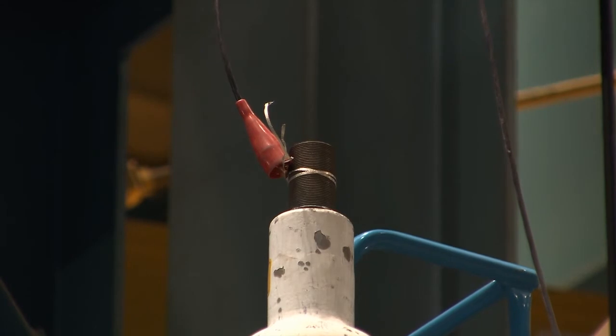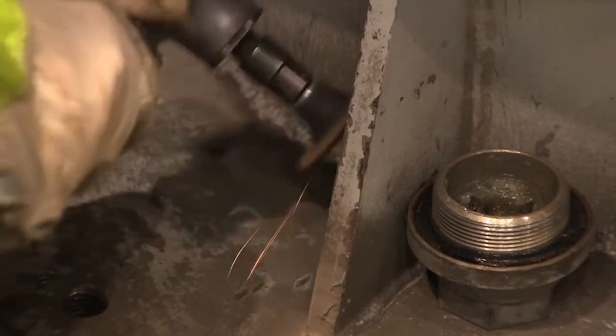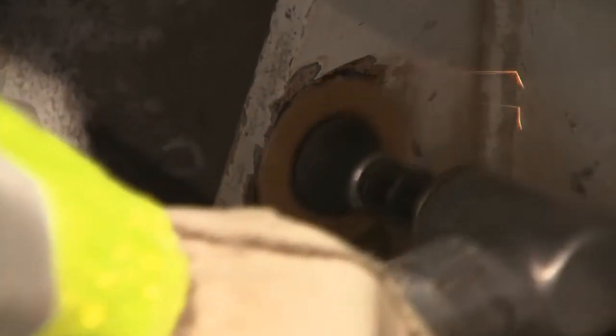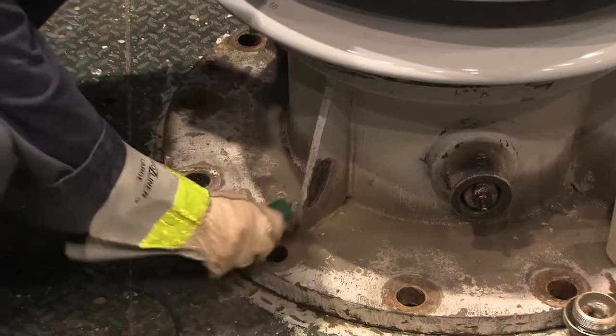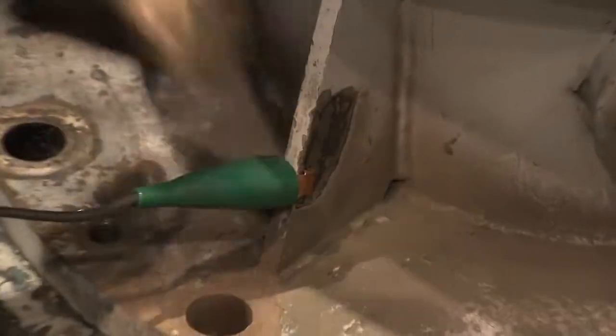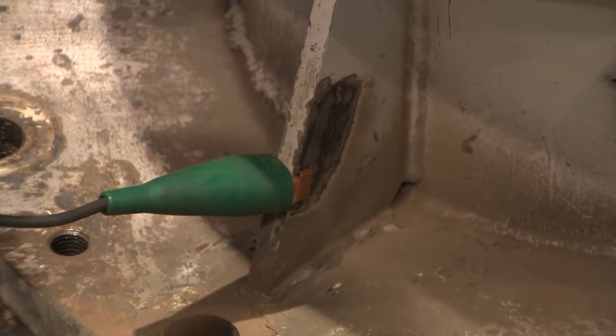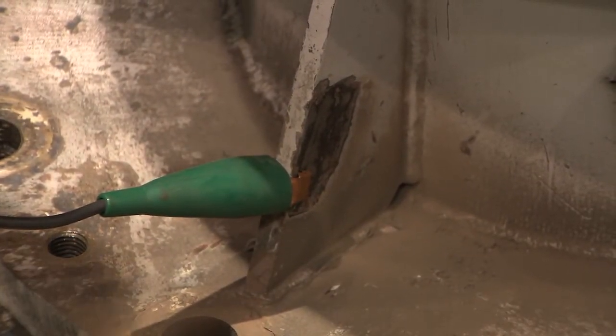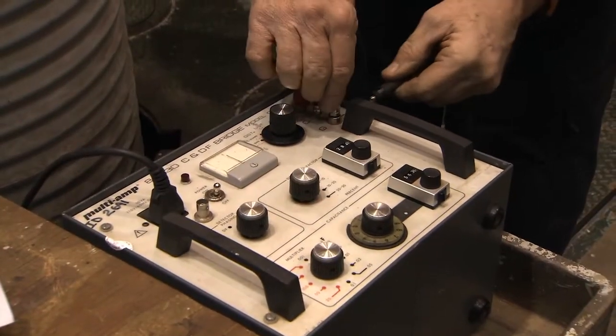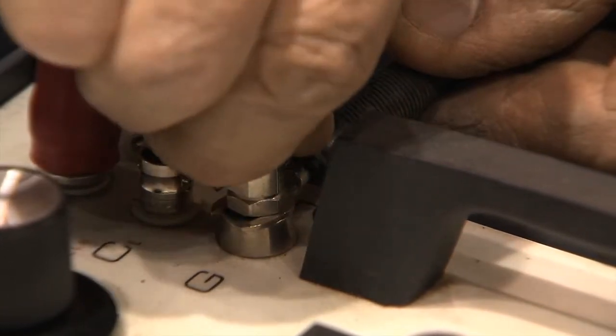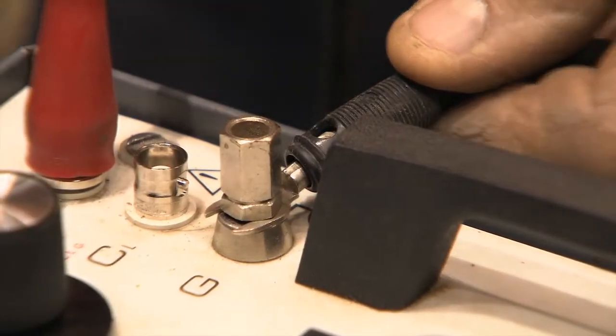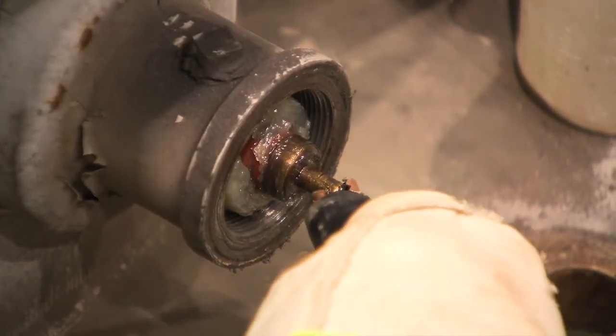In order to make a proper ground connection to the bushing, it may be necessary to grind off the layers of paint on a small section of the flange, so that a section of bare metal is exposed. Once the metal has been exposed, connect one end of the ground cable, the green lead, directly to the bare metal on the flange. Connect the other end to the terminal labeled G on the capacitance and dissipation factor bridge. This terminal is at the bottom of the 3 terminals on the bridge.